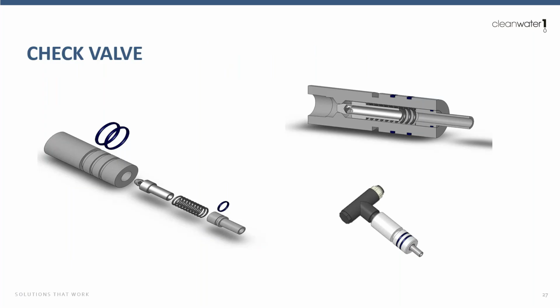We want to have a spare check valve on the shelf. This will allow you to basically remove the existing check valve, place the spare shelf check valve on the system. Generally, this takes only 30 seconds to a couple of minutes to do. And then you can clean the check valve that was on the system.